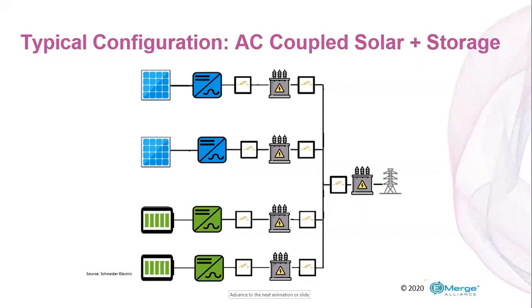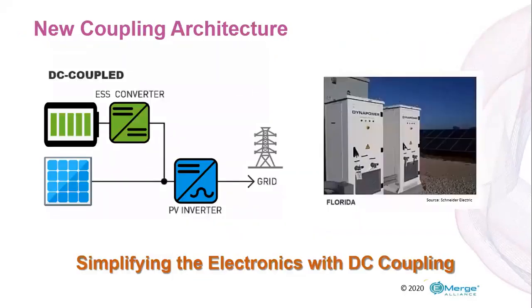In any case, people did start to move, even early in the game, to inverter technology that only dealt with the final result, and the combination of DC sources like PV and battery were actually managed in a DC bus format, so that you only needed a single inverter conversion for the final grid tie or to the AC tie back to loads. So this did start to simplify the electronics a little bit, where you'd have these internal DC coupled buses.